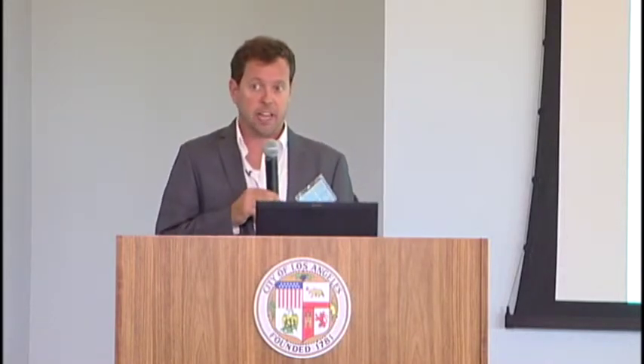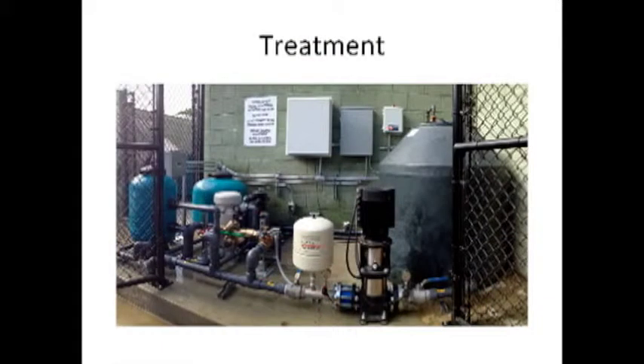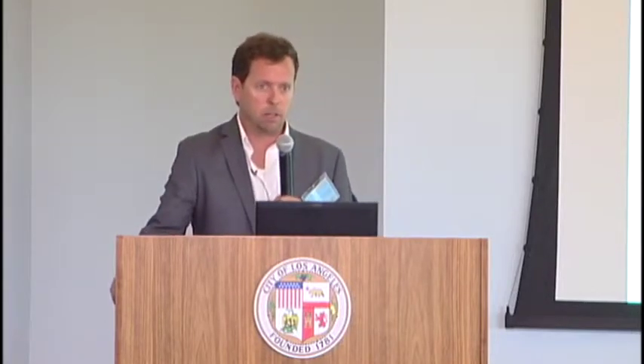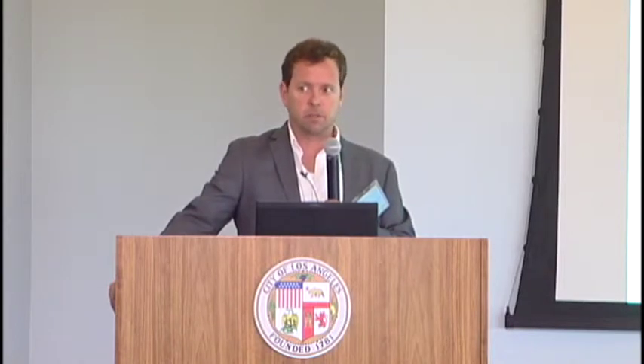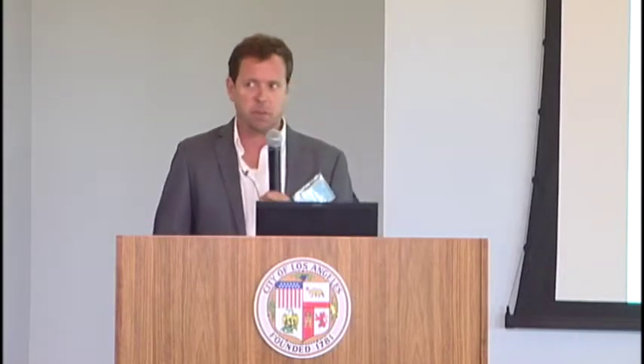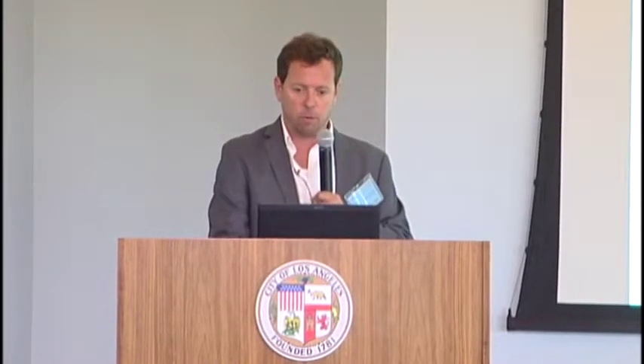From the cistern to the end use, some sort of treatment is always used. At this Santa Monica project, we used quite extensive treatment — various levels of physical filtration and disinfection — because we were using the water in a position where there's potential for human contact: flushing toilets. On smaller scale projects or projects where there's subsurface irrigation, substantially less treatment is necessary, and it definitely affects the economics of the overall project.